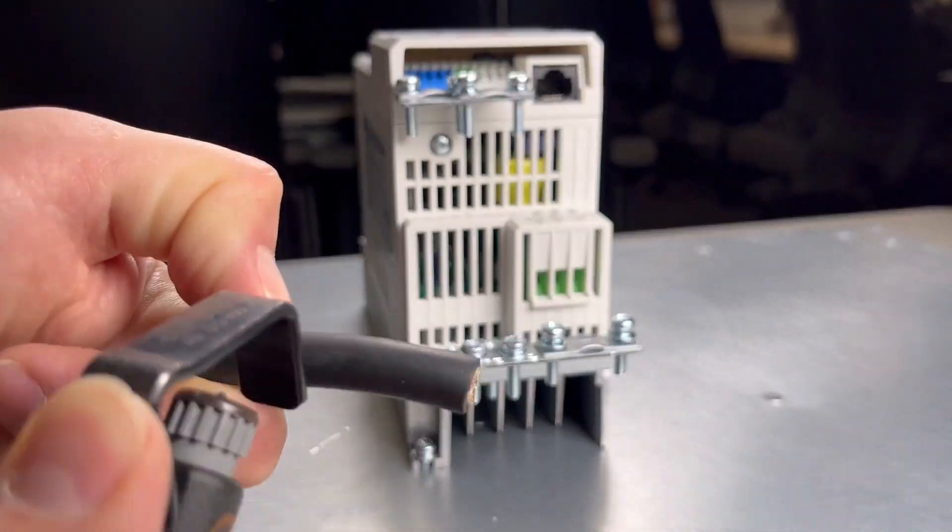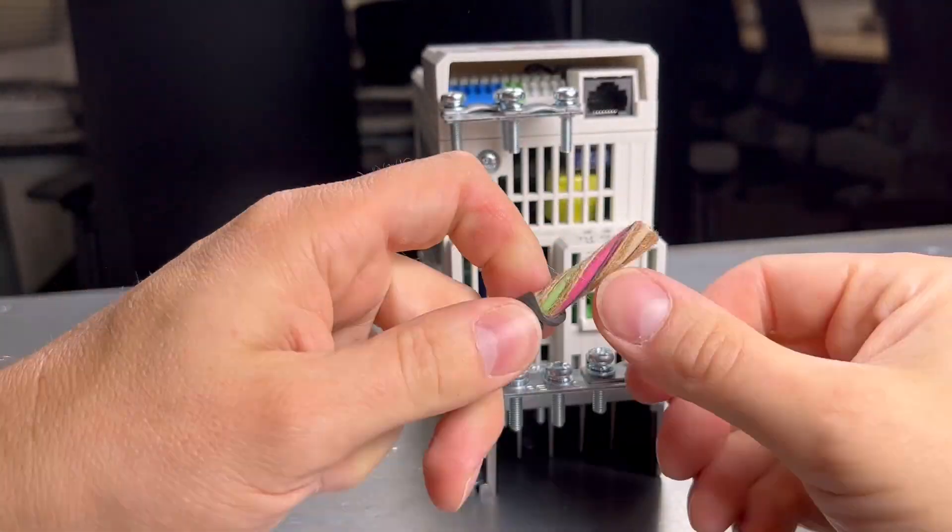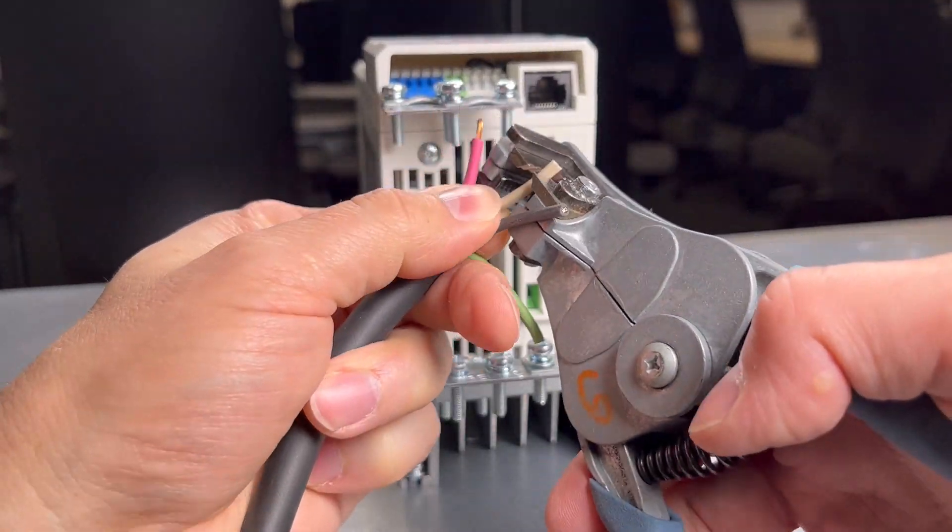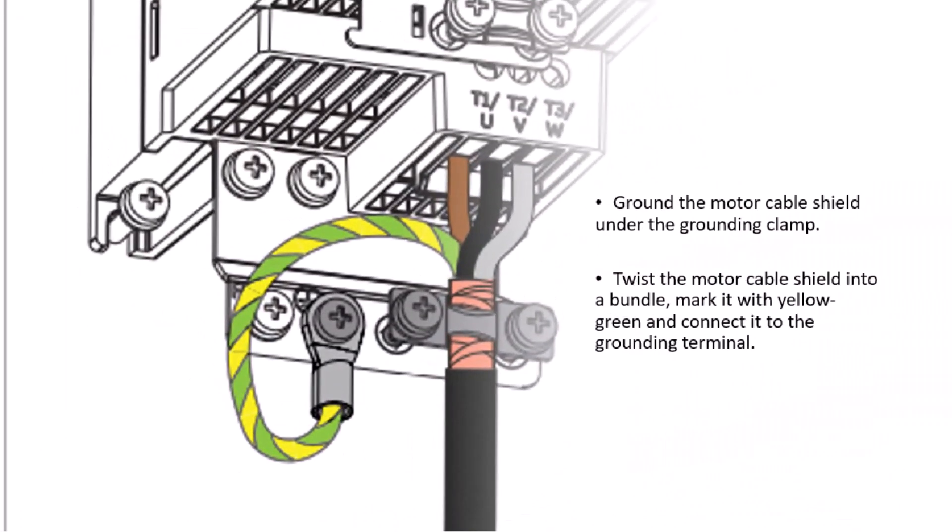Prepare the motor cable conductors. Ground the motor cable shield under the grounding clamp. Twist the motor cable shield into a bundle, mark it with yellow-green tape, and connect it to the grounding terminal.